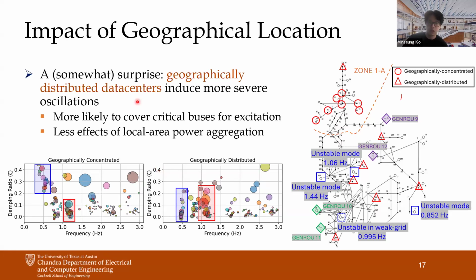and the size of each circle shows the magnitude of the oscillations. Compared to the concentrated case, in the distributed case you can see a larger magnitude of oscillation at around 1 Hertz. And one interesting point between the concentrated and distributed cases is a noticeable difference in the damping ratio at the 0.5 Hertz level. Although they have a similar magnitude of oscillation at 0.5 Hertz, they have very different damping ratio levels.